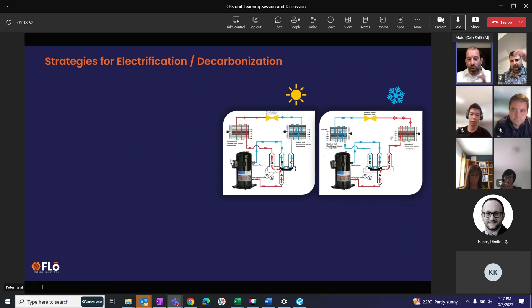Now, refrigeration source heat pump, you would consider or think of as reclaim, or reclaim like you're doing in this case. But in truth, it is a heat pump as well. One of the reasons I want you to start thinking about it in that way is that regulatory bodies, government rebates, and insurance companies all like the word heat pump. None of them know what reclaim is, they don't have the first clue because we only use it in the grocery industry. So it is a heat pump, it is a compressor that is moving heat from cases to an exhaust point, and we're just tapping into that. By using this term, you get better acceptance of the concept and the technology. So if you get to the point where you want to remove your auxiliary heat altogether because you're hoping we can get enough heat from these other sources, these are the terms to use because they will help a lot. And technically it is valid. So that's the different types of them.